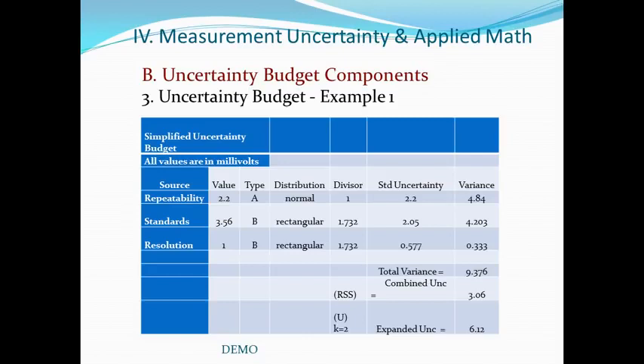The next one down is resolution, and if you recall, that is the application for a rectangular type of distribution. We have shown a value of 1 here, which means that the actual resolution of our meter or our measurement would be equal to plus or minus 1, or the total value is 2. This gives us an A value of 1, and so we have again the resolution as being a type B, rectangular distribution, and again it yields a divisor of the square root of 3. This gives us standard uncertainty of 0.577. Squaring that gives us 0.333 as the variance.